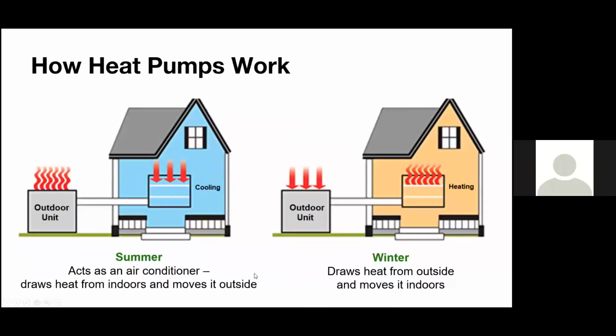So here's an example of a typical house. On the left, in the summer, you have your outdoor unit or your condensing unit rejecting heat. It might be 95 degrees outside, but you've compressed that refrigerant so much that it's at 150 degrees, so it's easily rejecting heat. And because of the exact refrigerant we use, once you start cooling it and it's under pressure, it'll become liquid. Then you bring that back inside and you can evaporate that refrigerant in the low 40s, 42, 43 degrees Fahrenheit, and using that, you're going to cool the air. On the right side, same system, same components, but that reversing valve kicked in, and now we're going the other way. So we're rejecting heat indoors and we're extracting heat from the outside.